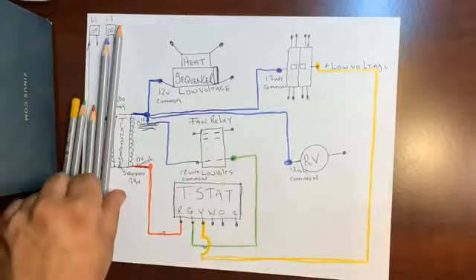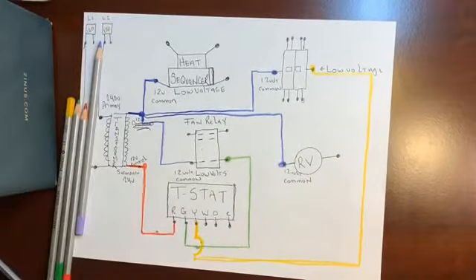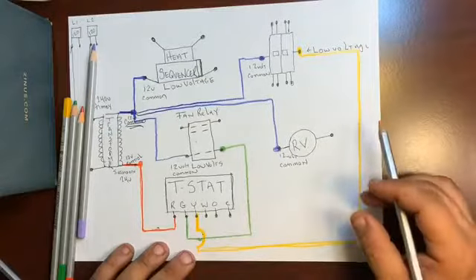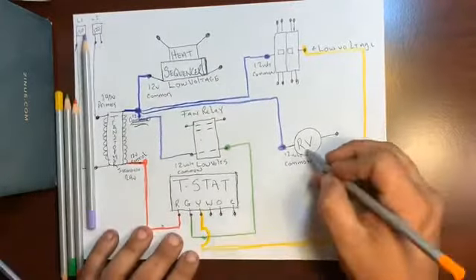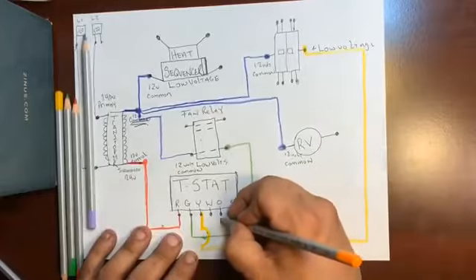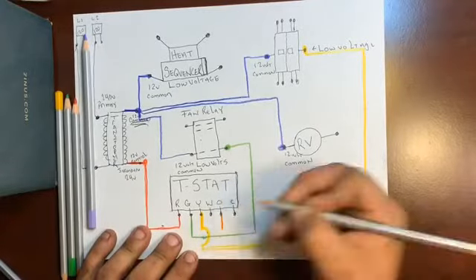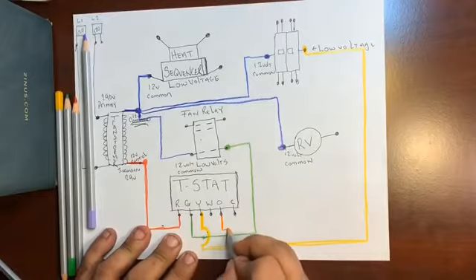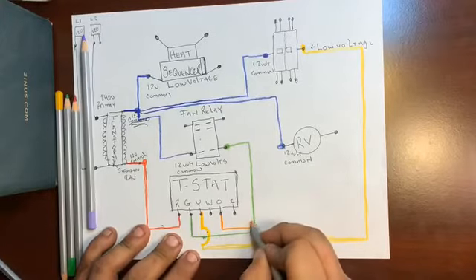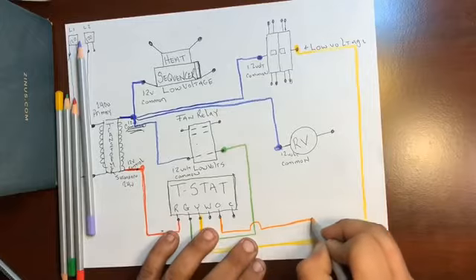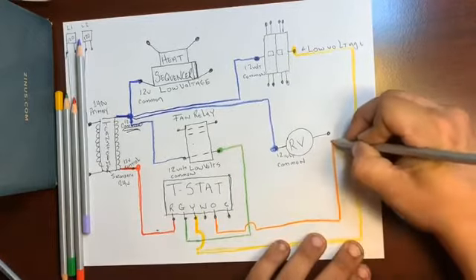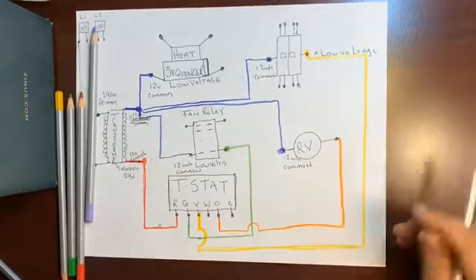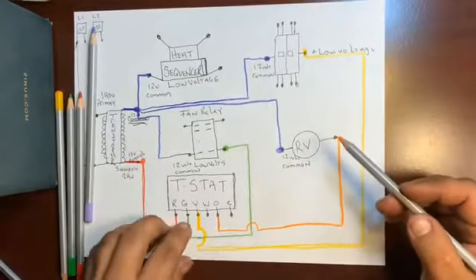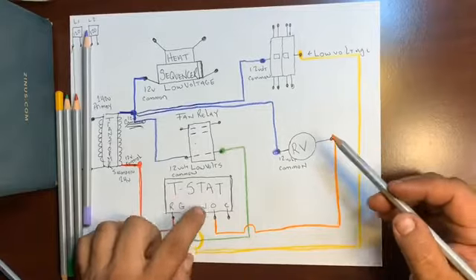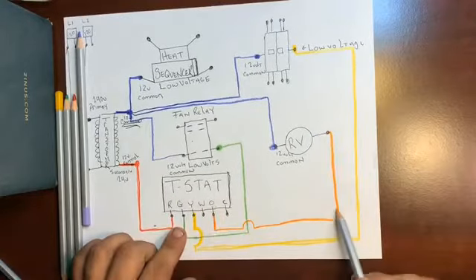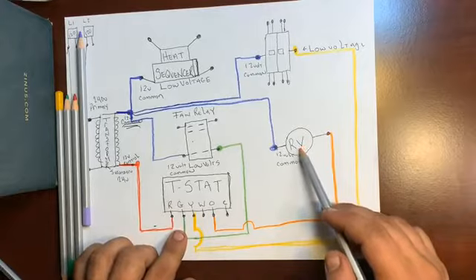Reversing valve. The reversing valve is what makes heat pump possible. It's switching it from heating to cooling. And this is controlled by the orange. Reversing valve gets the orange wire. So then orange will come down from orange. Looks like we're gonna be able to make a right, jump it, very good, bring it over, and then up. There's your orange wire. So now, when Mr. Thermostat says, hey, turn on heat pump mode or turn off heat pump mode, it'll energize the voltage through the orange wire, and now the reversing valve will have its 24 volts.